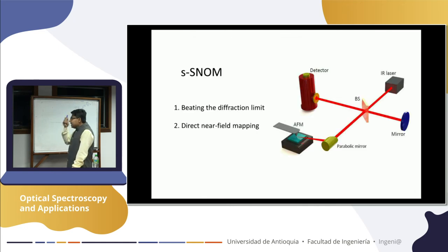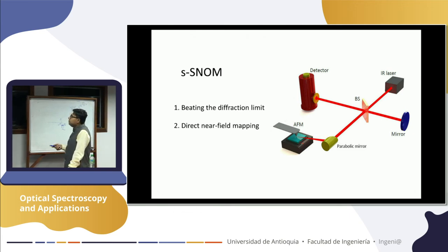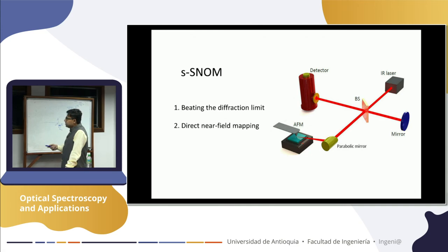So what does it look like? We spend time on that. This is a Michelson interferometer, right? You need to have a two beam path. One, you excite your sample with direct laser. Don't look at this one yet. Just direct laser, and then some portion of the light bounces off this mirror and creates another path. Your detector sees light coming this way and light coming this way, and creates an interference pattern. We've gone through that process, that we have a correlated signal and the Fourier transform to get the wavelength dependent absorption or reflection. That's what we did in FTIR. That is a very common technique we understood.